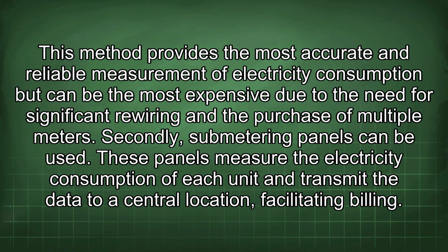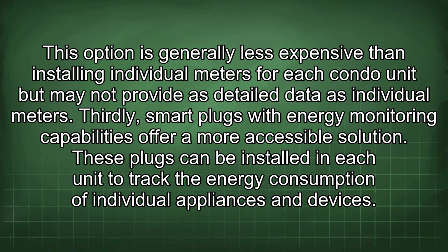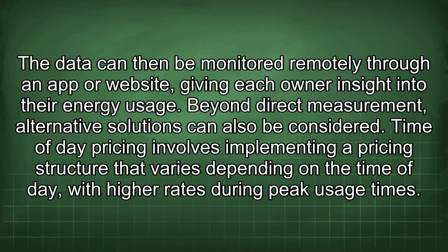Secondly, submetering panels can be used. These panels measure the electricity consumption of each unit and transmit the data to a central location, facilitating billing. This option is generally less expensive than installing individual meters for each condo unit, but may not provide as detailed data as individual meters. Thirdly, smart plugs with energy monitoring capabilities offer a more accessible solution. These plugs can be installed in each unit to track the energy consumption of individual appliances and devices. The data can then be monitored remotely through an app or website, giving each owner insight into their energy usage.